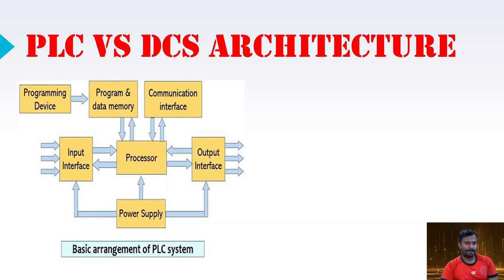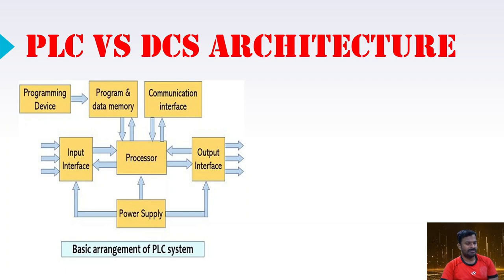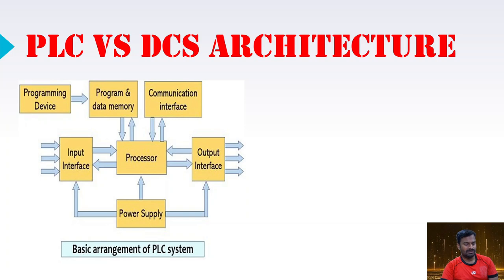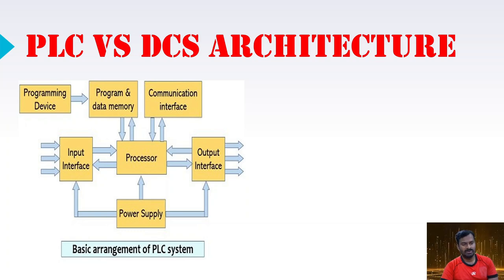The PLC has memory to store the program and execute data, and it has communication capability to connect to field devices like VFDs and other controllers. The input interface connects to field devices like sensors — analog sensors connect through an analog-to-digital converter before data reaches the processor, while digital signals are also conditioned to readable voltage and current levels before going to the processor.